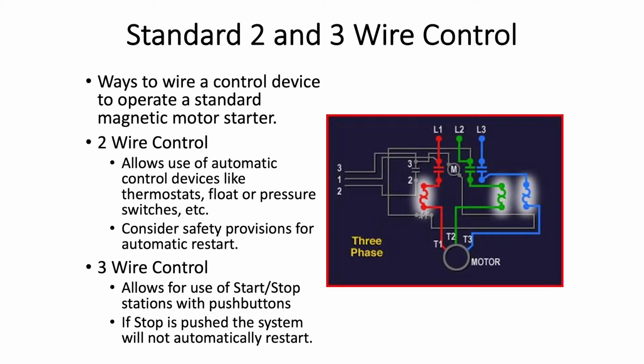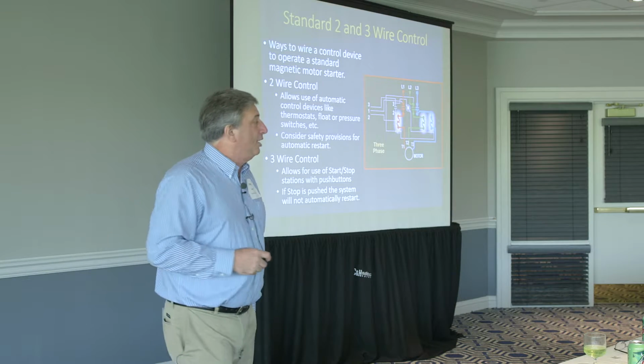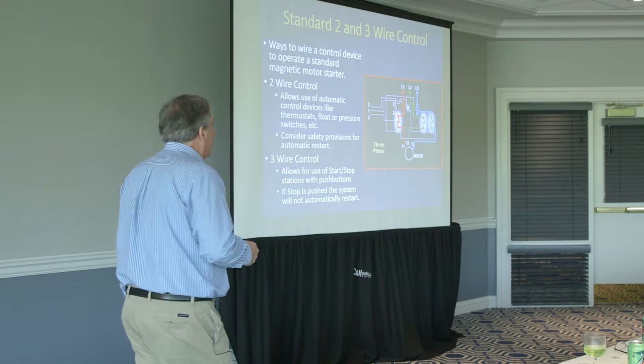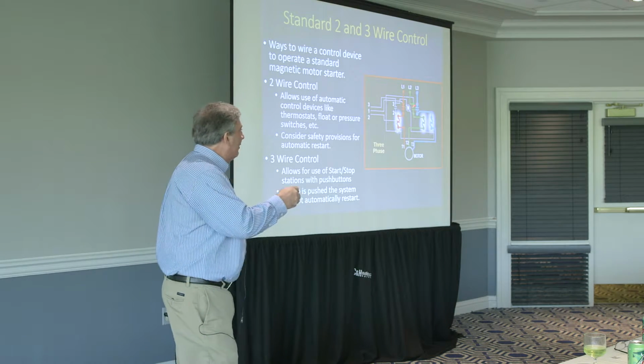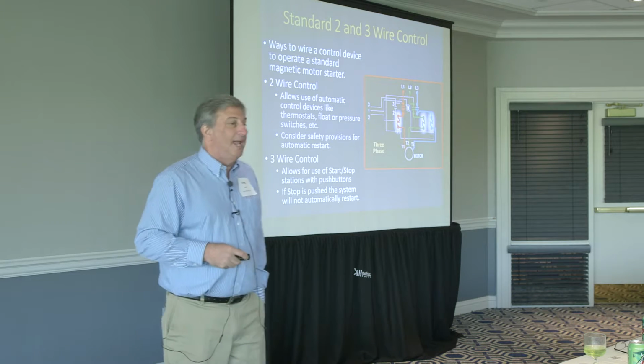2-wire and 3-wire control, just to think about that. 2-wire control allows use of automatic control devices. 3-wire control, I'm going to use a start-stop station with push buttons. If the stop is pushed, the system will not automatically restart. So that start-stop station, if my magnetic starter trips out because an overload tripped out, it doesn't matter.